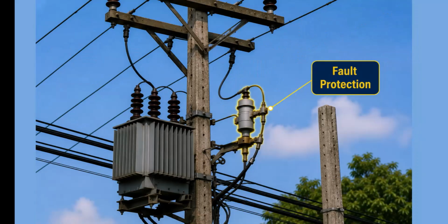Then look at this protection equipment. A power system has to be designed with the assumption that faults can happen. A conductor can contact another conductor. Equipment insulation can fail. A tree branch, animal, or damaged component can create an abnormal electrical condition. When that happens, we do not want the fault current to flow continuously. Protection equipment helps detect or interrupt abnormal conditions and isolate the affected part of the system. Now, when you recognize a device associated with protection, you should think fault protection.